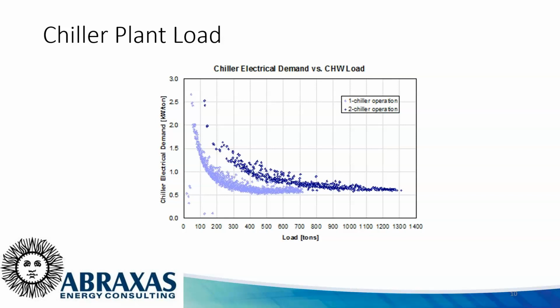One other point about creating regression models when looking at data like this, particularly for chillers or HVAC: I don't like seeing curves like this, because that kind of curve, if you try to fit it in Excel, there's no curve that will really fit those shapes. If you notice, we have load on the x-axis, and load is also a factor in the data on the y-axis - it's tons on the x-axis and kW per ton on the y-axis. Don't have tons on both axes.